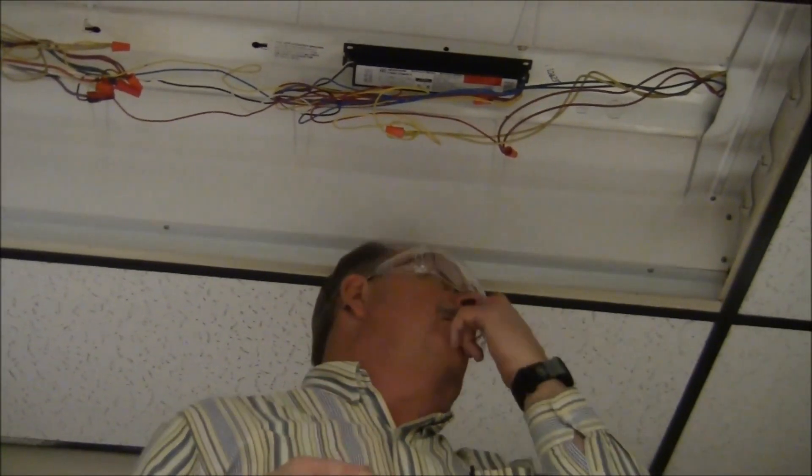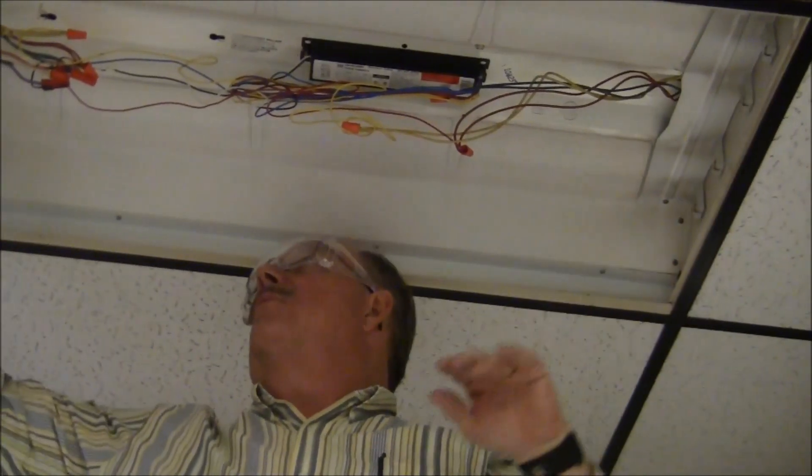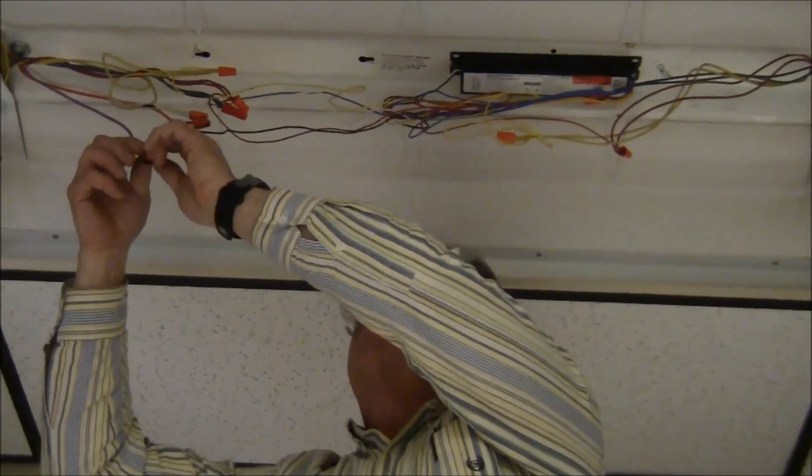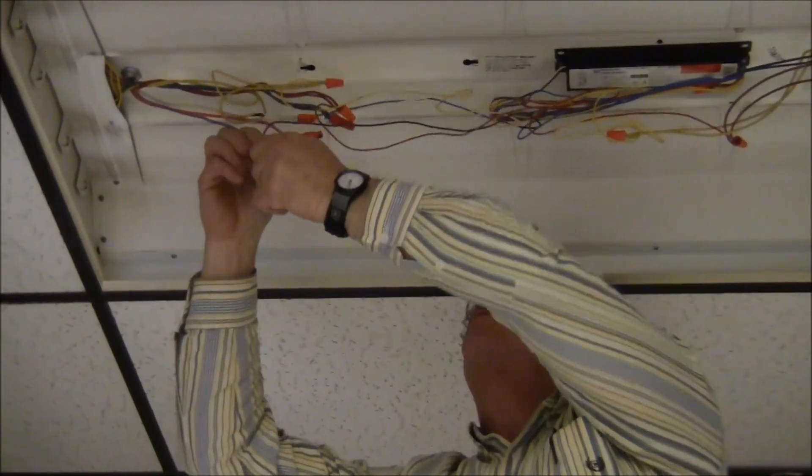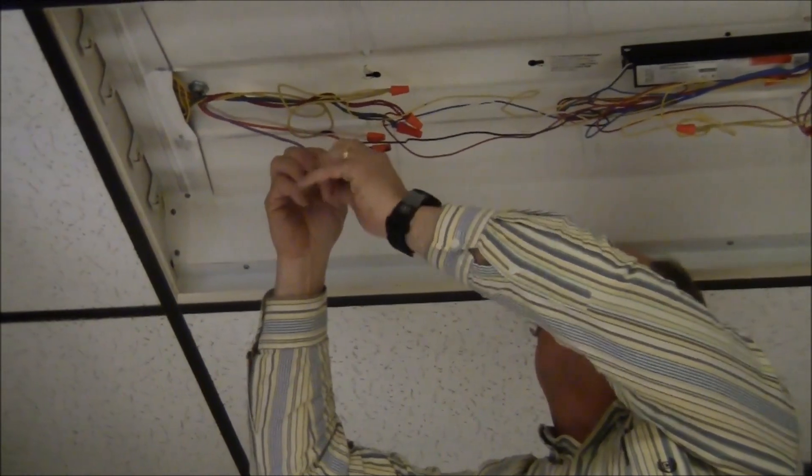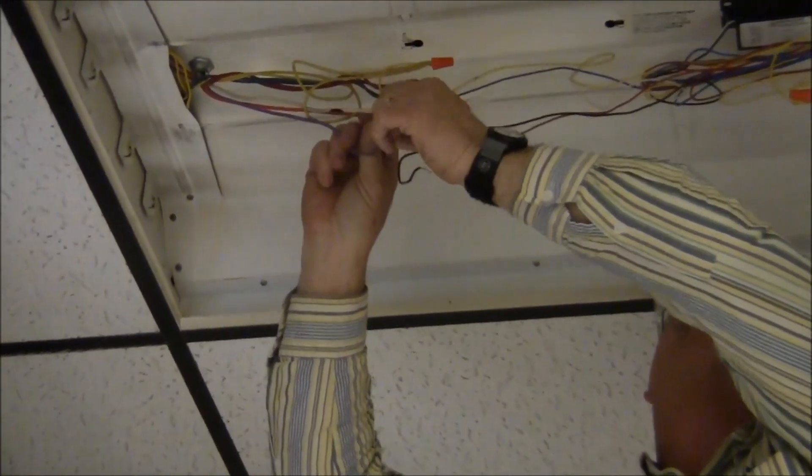The LED bulb is going to require us to energize one set of pins with the line voltage. In this particular case, we have 277 volts coming into the fixture, so the first thing I want to do is disconnect the main power from the ballast and get the ballast out of the system.